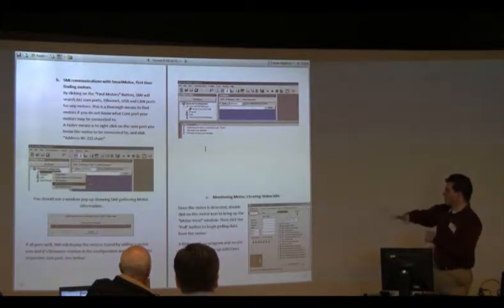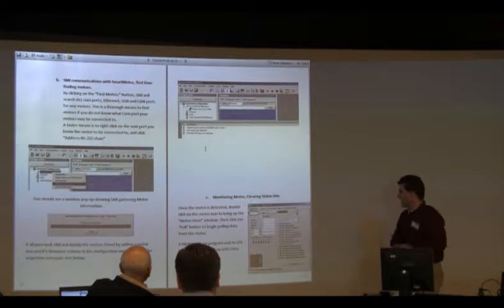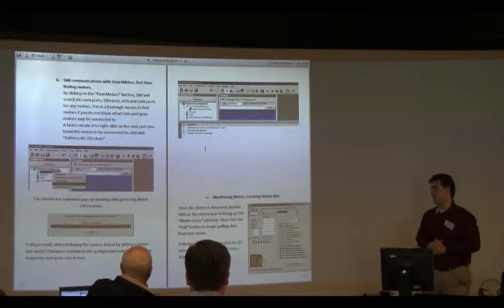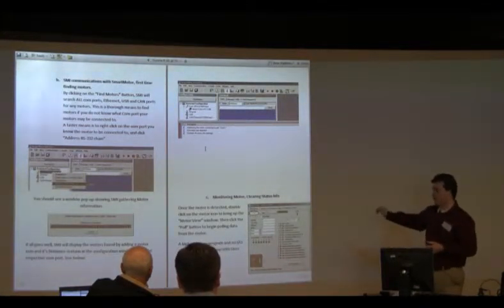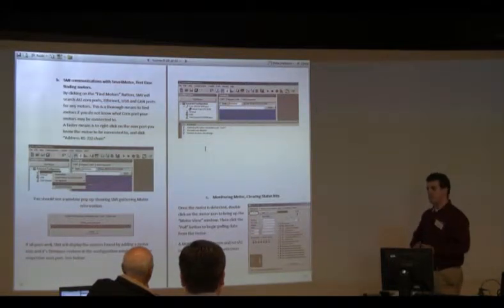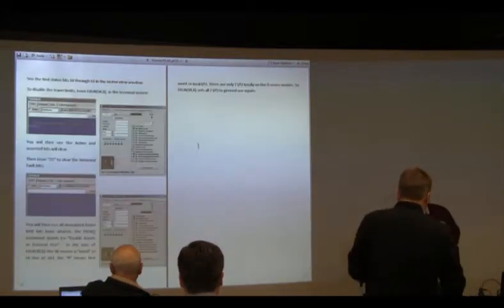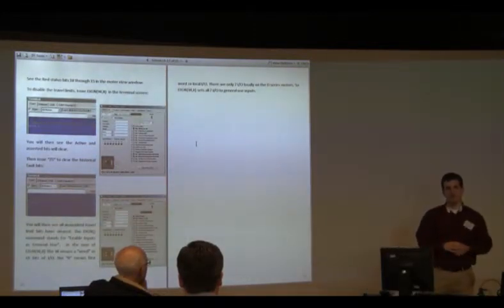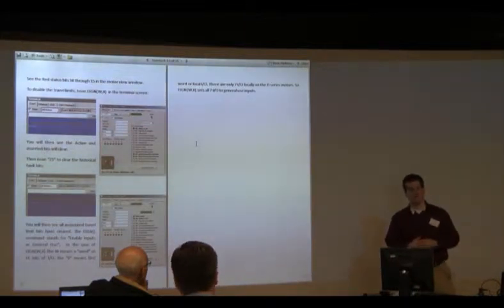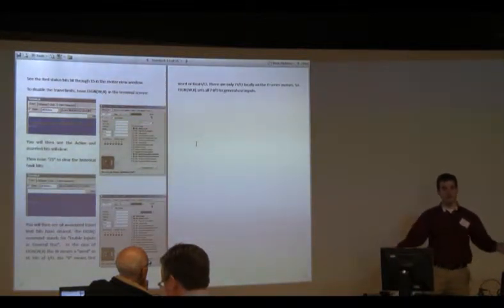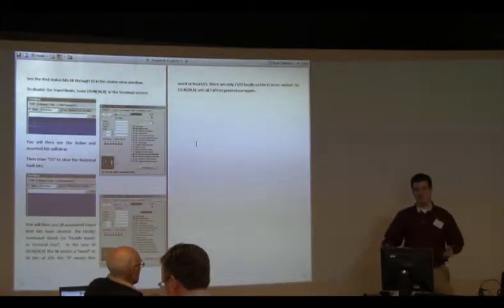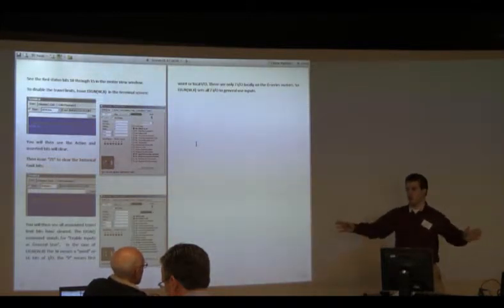So we double click on motor 1, we click on pull. And what will happen is you should see a bunch of red lights come on the side there. You'll see drive motor off, and then you'll see a whole bunch of indicators for the positive and negative limits. The smart motor, by default, will have limit switches enabled. And the limit switches would be normally closed to ground. Now, if you have nothing connected to the motors, it looks like the limit switches are open. The motor thinks it hit both limits at the same time, and it goes, holy God, something's gone wrong. I'm not going to move.